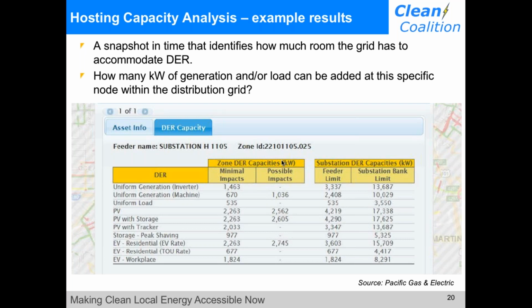The hosting capacity for a specific distribution circuit is not a fixed value. It's a range depending on the DER technology or technologies added to the grid, as well as the exact location where that DER is sited. This is shown for a specific section of Pacific Gas and Electric's grid. The DER listed on the left can offer both generation and load, and you can see what those various levels are for those DER technologies or portfolio of technologies. Being able to proactively understand these limitations can help make the market operate more efficiently and design and size the right project with the right technologies at the right location on the grid.